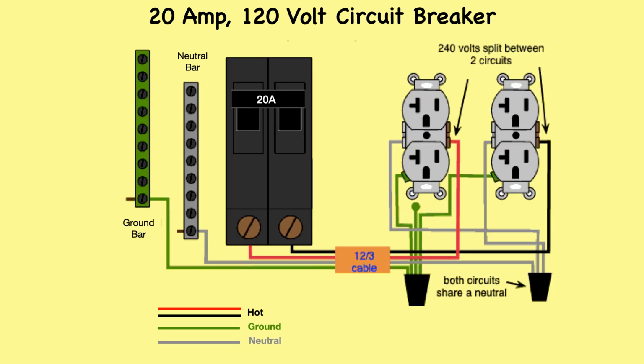This arrangement is for a 20 amp, 120 volt double receptacle circuit with a shared neutral wire. This arrangement is typically used in a kitchen, where 2 separate appliance circuits are needed in close proximity to each other. Notice that the breaker is a ganged, or double pole, single throw breaker, which means that it switches, or trips, both circuits at the same time.